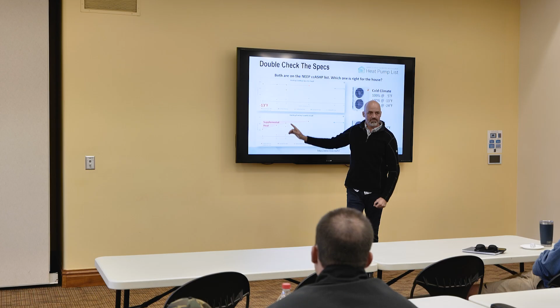Number one, make sure you have a -13 number on the NEEP list. Number two, that they actually do the Manual J and Manual S, and that the software demonstrates that each zone, or the overall, meets the capacity. Those two things alone, at your design conditions, will avoid most of the issues going in.